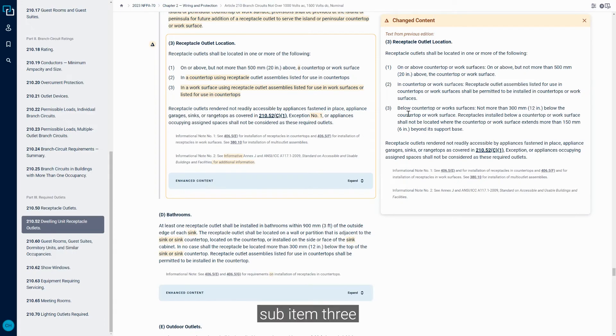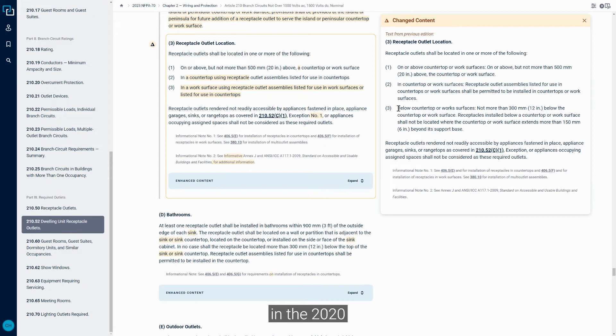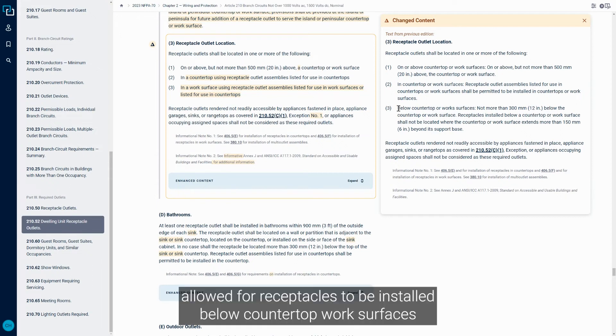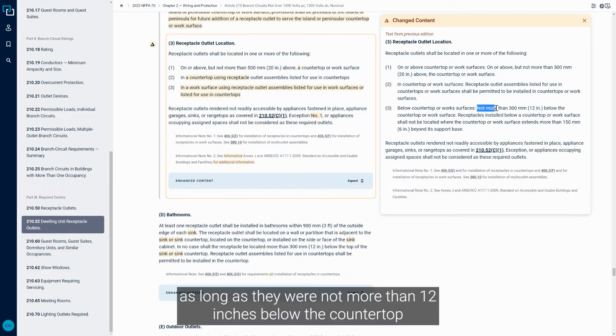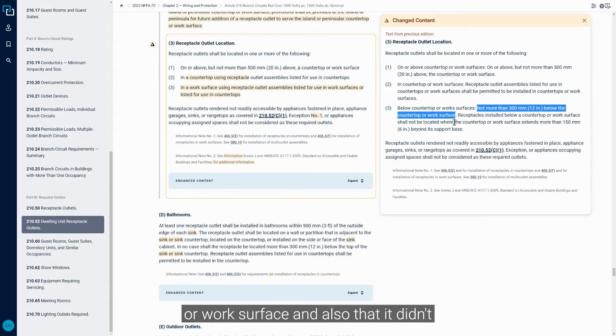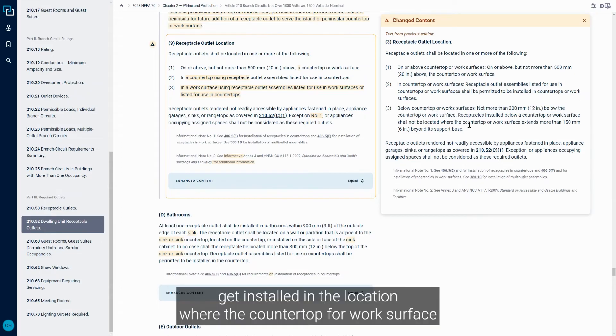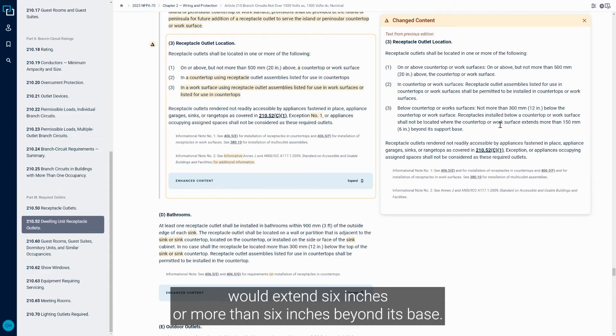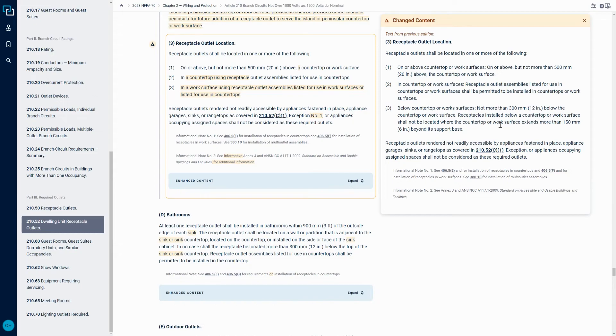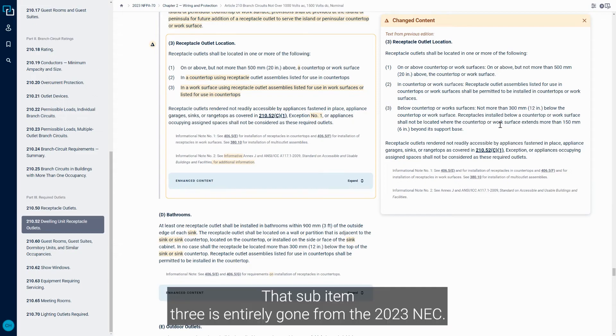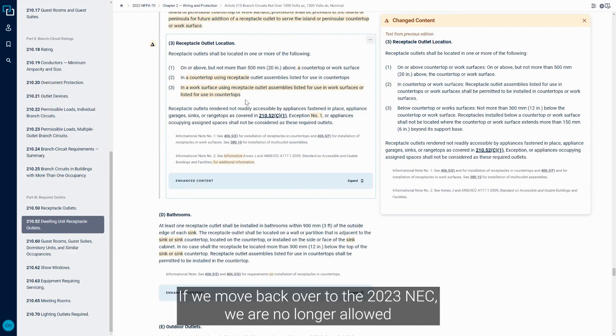Sub-item three in the 2020 allowed for Receptacles to be installed below countertop work surfaces as long as they were not more than 12 inches below the countertop or work surface, and also that it didn't get installed in a location where the countertop or work surface would extend six inches or more than six inches beyond its base. That sub-item three is entirely gone from the 2023 NEC.